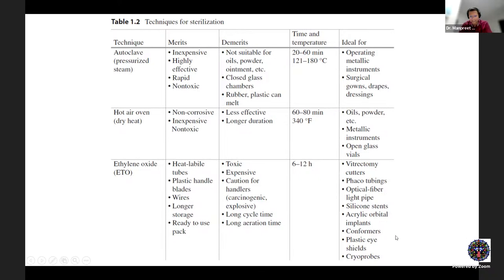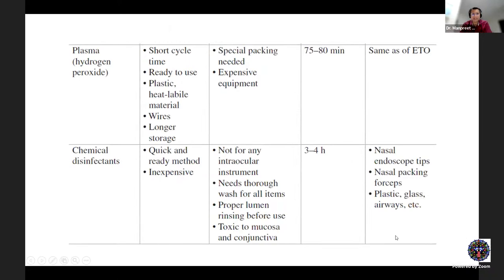Plasma sterilization uses hydrogen peroxide. It has a shorter cycle than ETO, produces ready-to-use packs, is suitable for plastic and heat-labile materials, and offers longer storage of up to six months. It requires special polypropylene or polyolefin packing and a dedicated packing machine. The machine costs approximately 50 to 75 lakhs but can serve a multi-specialty institute.